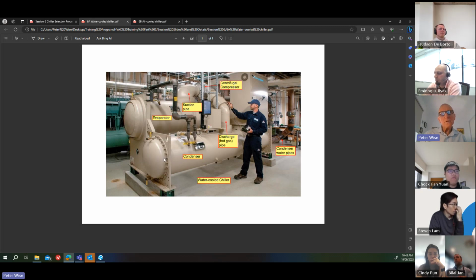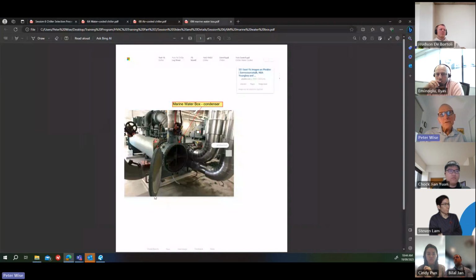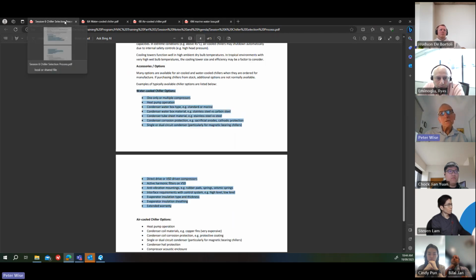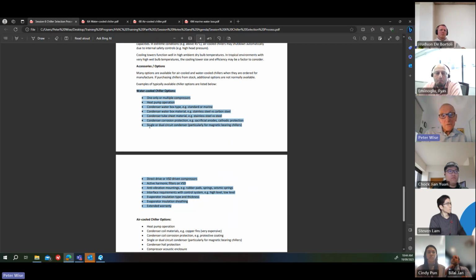And they're very heavy to put on the floor and lift back and line up again and put back on. So you can get what they call a marine water box. In this case, this is the water box here, and it's mounted on a hinge attached to the chiller. So you still have to undo all the nuts, but you can just swing it out of the way, do the cleaning that you need to do inside here, and then just swing it back and bolt it up again. So it's much easier, but it's quite expensive. So typically on a water-cooled chiller, a marine water box, it'll be several $1,000s. It might be 5,000, might be more, depending on the size of the chiller.